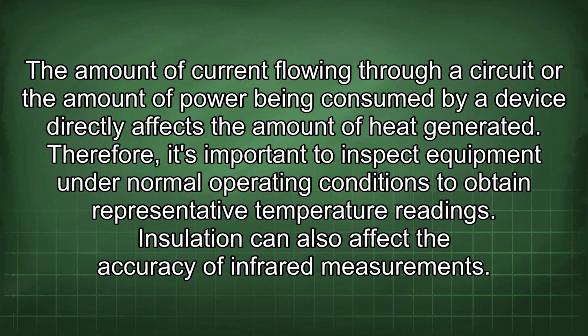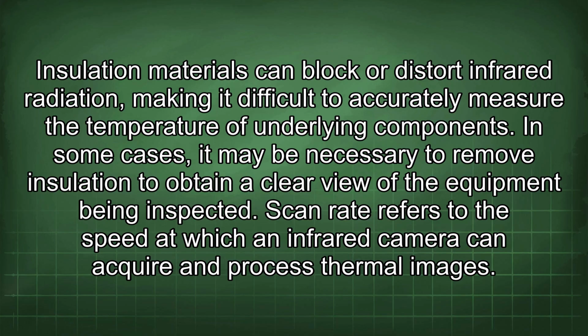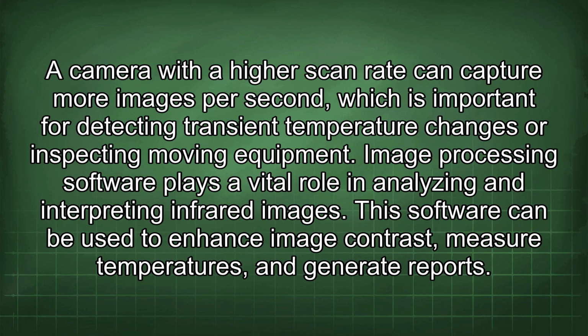Insulation can also affect the accuracy of infrared measurements. Insulation materials can block or distort infrared radiation, making it difficult to accurately measure the temperature of underlying components. In some cases, it may be necessary to remove insulation to obtain a clear view of the equipment being inspected. Scan rate refers to the speed at which an infrared camera can acquire and process thermal images. A camera with a higher scan rate can capture more images per second, which is important for detecting transient temperature changes or inspecting moving equipment.